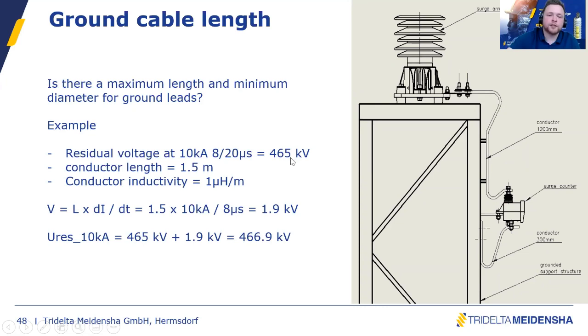465 kV initially, plus 1.9 kV for the inductive voltage drop. We will have the result of 466.9 kV. So you can calculate by your own and then recalculate the protection level that is provided by the surge arrestor and compare this to your BIL of the system, of the transformer, or whatever you're protecting with the surge arrestor.